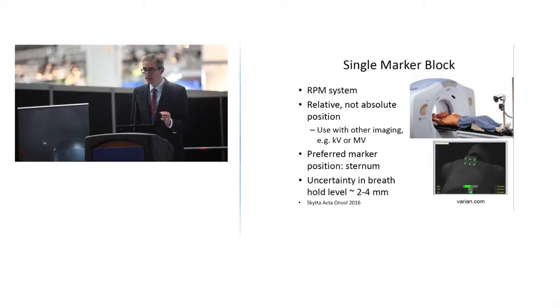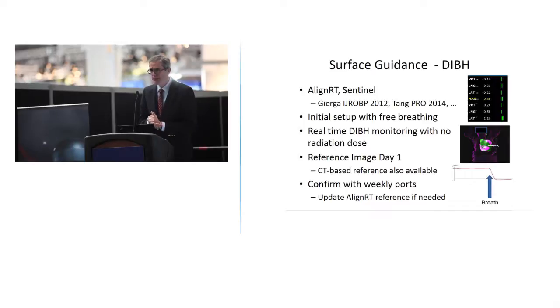Then we can use the full surface from the AlignRT product or other products like the Sentinel product. I've just listed a couple of publications here from our group and also from the North Carolina group. What we do is we have two reference images: the initial setup image under normal breathing conditions and then the reference image for the breath hold. So first the patient is put in a position to take a breath and then we monitor the patient to make sure that they then take a breath. Of course there's no radiation dose here. You can see the image here and the dark purple area is the region of interest that we're registering.